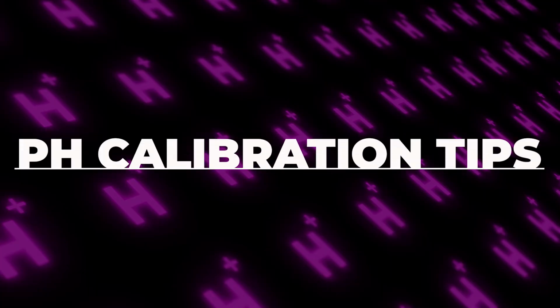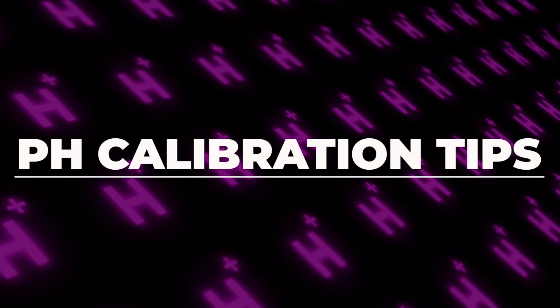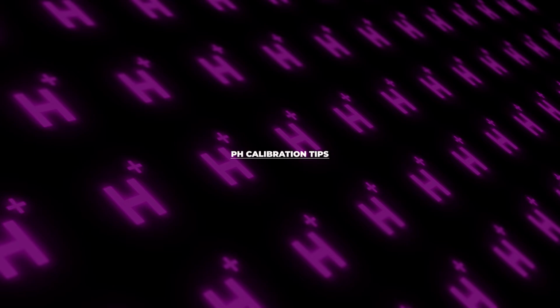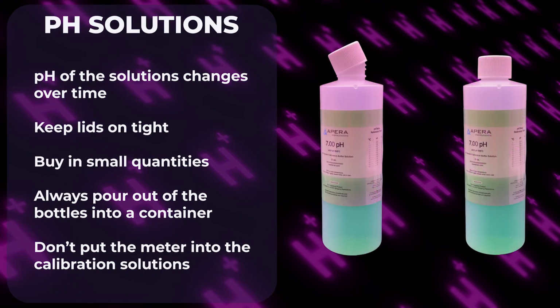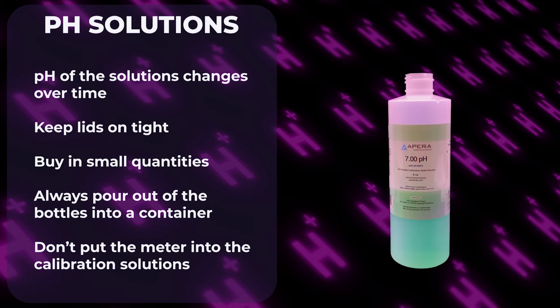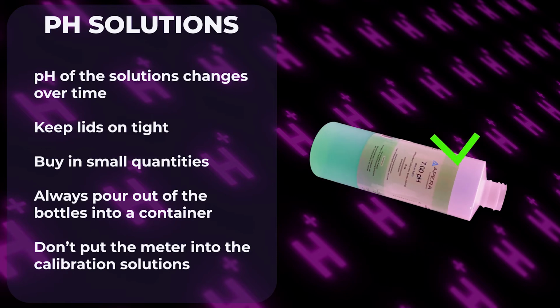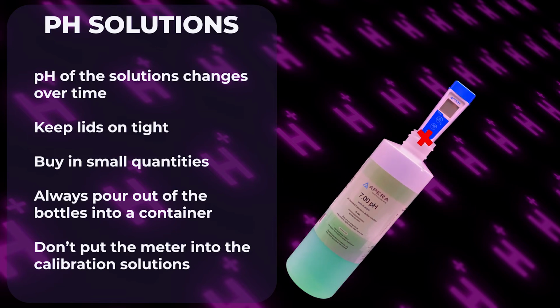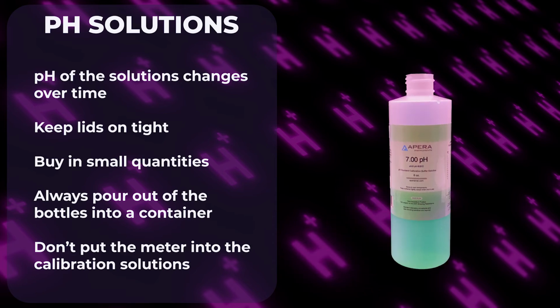To finish up, I want to give you some tips to help keep your pH meter calibrated and to make sure your calibration doesn't drift without you knowing it. First, the pH of the solutions will change over time, especially as air comes into contact with the solution. So keep a tight lid on the bottle and buy them in small quantities to keep them fresh. Also, only pour out from the bottle what you need. Don't put the probe into the bottle. This could introduce contamination into the bottle that will definitely change the pH of the solution over time.